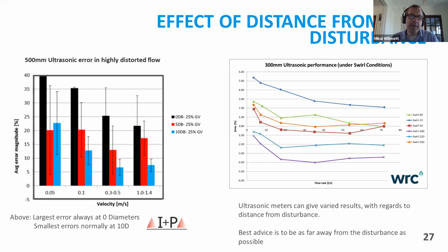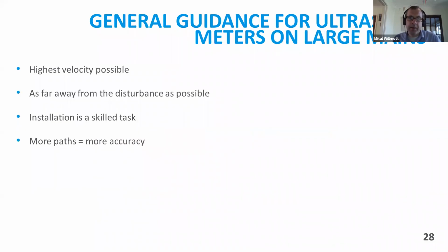Now, there's a few things that we can do to make sure that we optimize our ultrasonic performance, because in many cases, ultrasonics will be the optimal meter, especially in places where you cannot turn off the main and you need to put a meter in there. Andy, if you'd just like to go on to the next slide. And so there's a few guidelines that I think is really important that we should remember when installing clamp-on ultrasonics. First of all, let's get the highest velocity possible. Let's get as far away from the disturbance as possible.